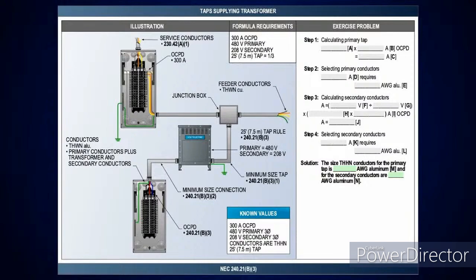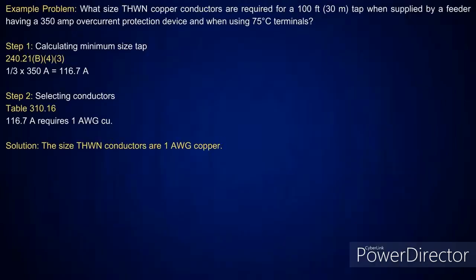And then right here, what do we got? We got a 480 volt primary, 208 volt secondary. It's a 25-foot tap, and you've got all your information here with a 300 amp overcurrent device. So basically, you know the primary is taken at a third for that 300 amp. The secondary, I need the ratio plus a third of what? The overcurrent protection device, which is 300 amps, and that'll give you your amperage. All right?